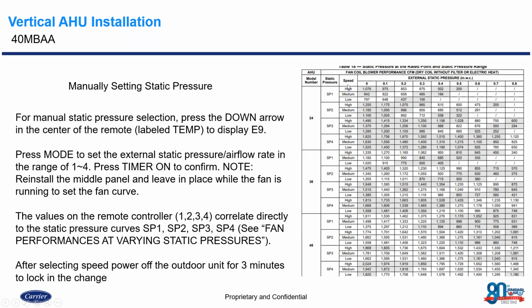Okay, now if we look over to the right here, it'll give you different fan speeds and the static pressure it's going to be at, corresponding with the CFM that it would deliver at that static pressure. So this is where you're going to use your chart and figure out what CFM and static pressure is going to match the CFM that you need to deliver to every single one of those zones that this air handler is serving. For example, if you needed, let's just say, 0.3 inches of static and you needed 1600 CFM, you would go to your SP4 setting, which means at 0.3 static, you're getting 1592, which is just a little bit under 1600 CFM, to deliver the proper airflow to the space.